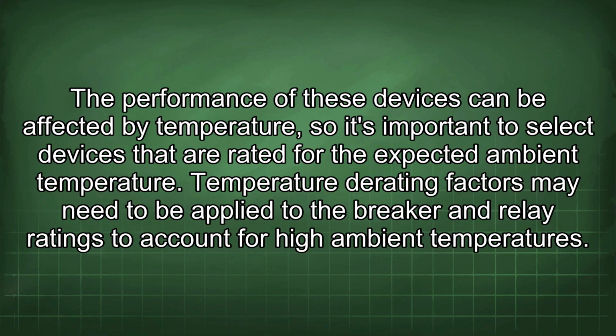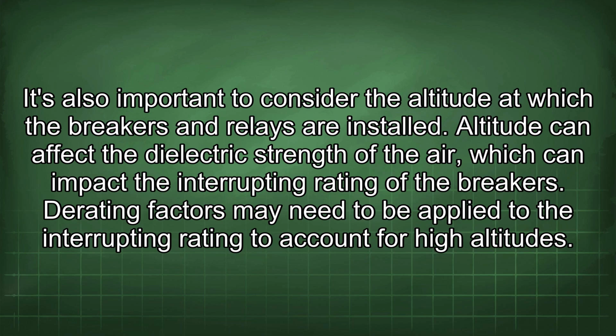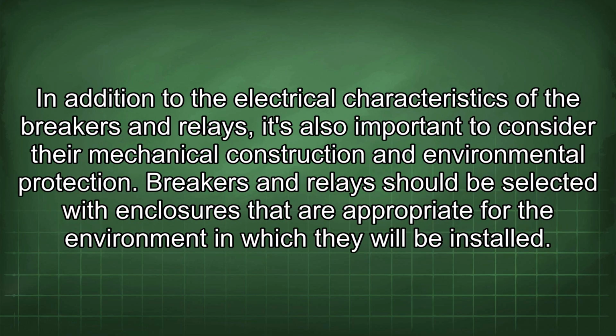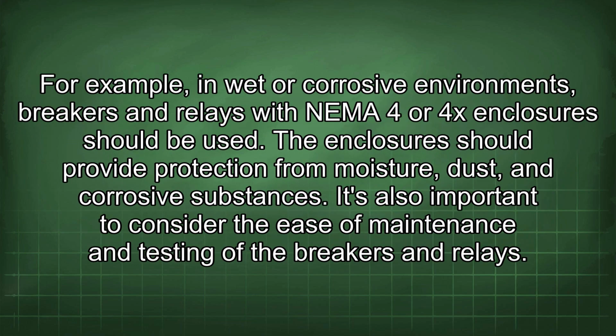for high ambient temperatures. It's also important to consider the altitude at which the breakers and relays are installed. Altitude can affect the dielectric strength of the air, which can impact the interrupting rating of the breakers. Derating factors may need to be applied to the interrupting rating to account for high altitudes. In addition to the electrical characteristics of the breakers and relays, it's also important to consider their mechanical construction and environmental protection. Breakers and relays should be selected with enclosures that are appropriate for the environment in which they will be installed. For example, in wet or corrosive environments, breakers and relays with NEMA 4 or 4X enclosures should be used.